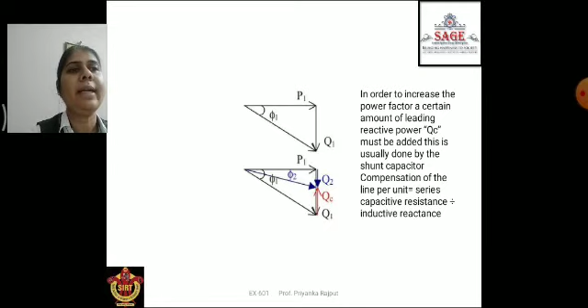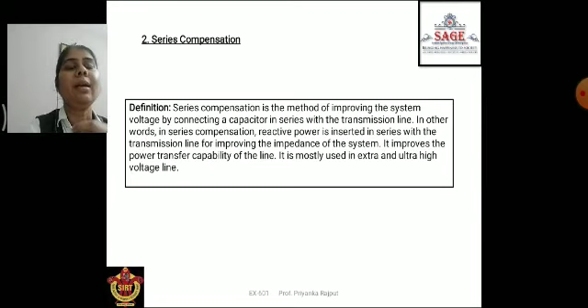A series compensator is the method of improving the system voltage by connecting a capacitor in series. In a shunt capacitor, we connect it in shunt, and in a series compensator we connect it in series with the transmission line. In other words, in a series compensator, reactive power is inserted in series with the transmission line for improving the impedance of the system. It improves the power transfer capability of the line. It is mostly used in extra and ultra high voltage.